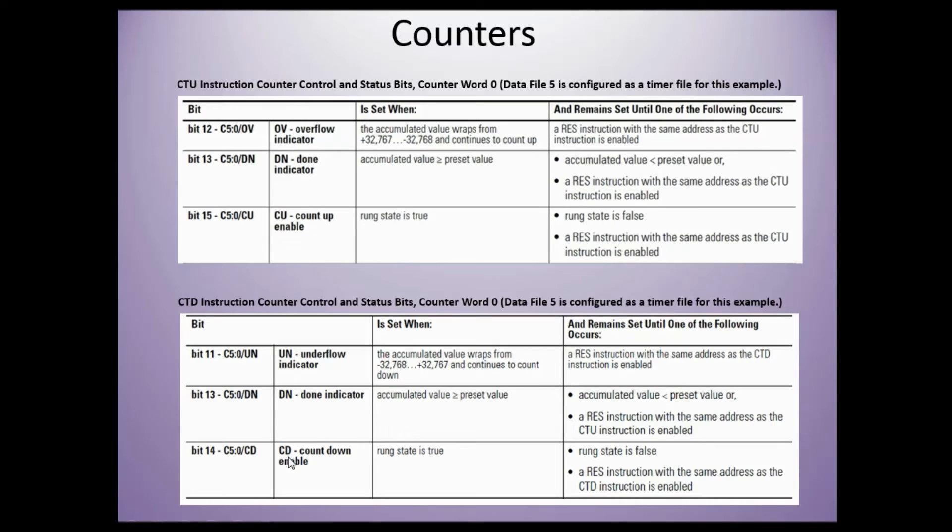Bit 14 is your countdown enable and this bit 14 for the CD is true every time the rung status is true. How to make that go false to go back to a zero state is that the rung state has gone false or a reset instruction is used.